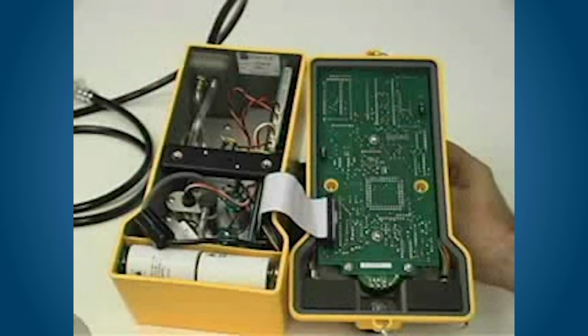The Eagle circuit boards analyze, record, control, store, and display the information collected by monitoring with the Eagle. The analog PCB provides the support circuitry for the Eagle sensors. It is located perpendicular to the base of the instrument case, in the same half of the case as the sensors and sample drawing system. Here you can see how the sensor leads connect to the analog PCB.